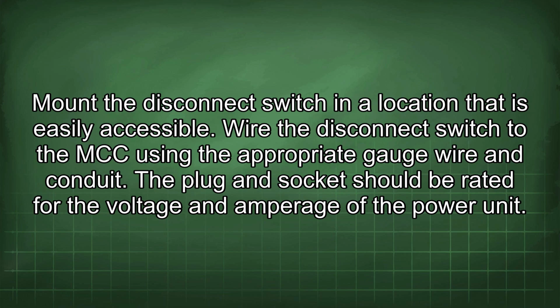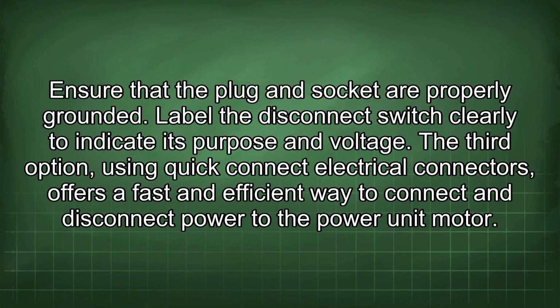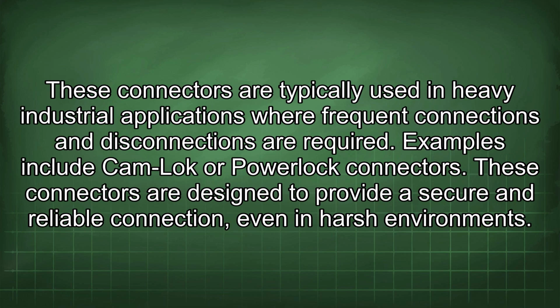Mount the disconnect switch in a location that is easily accessible. Wire the disconnect switch to the MCC using the appropriate gauge wire and conduit. The plug and socket should be rated for the voltage and amperage of the power unit. Ensure that the plug and socket are properly grounded. Label the disconnect switch clearly to indicate its purpose and voltage. The third option, using quick connect electrical connectors, offers a fast and efficient way to connect and disconnect power to the power unit motor. These connectors are typically used in heavy industrial applications where frequent connections and disconnections are required. Examples include Cam-Lok or Powerlock connectors. These connectors are designed to provide secure and reliable connection, even in harsh environments.